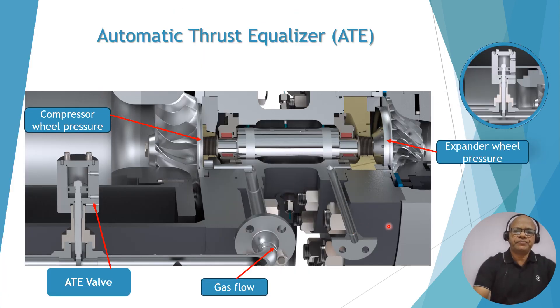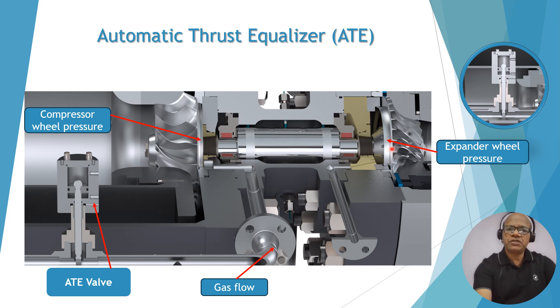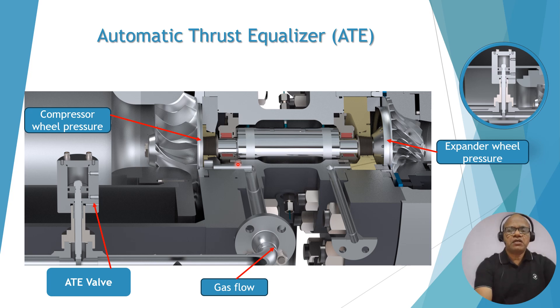Now looking at the cut view of the expander-compressor arrangement — this is the expander and this is the compressor, both connected to a single shaft. You can see the wheel pressure of the compressor and the wheel pressure of the expander. This is the thrust collar of the shaft, and this is the bearing for the compressor side and the expander bearing on the other side. There is a minimum clearance at the thrust faces of the shaft, where oil is circulating, creating oil thrust pressure on both the compressor and expander side bearings, both connected to the ATE port. The compressor wheel pressure — where process gas acts — is connected through the ATE to the suction of the compressor.